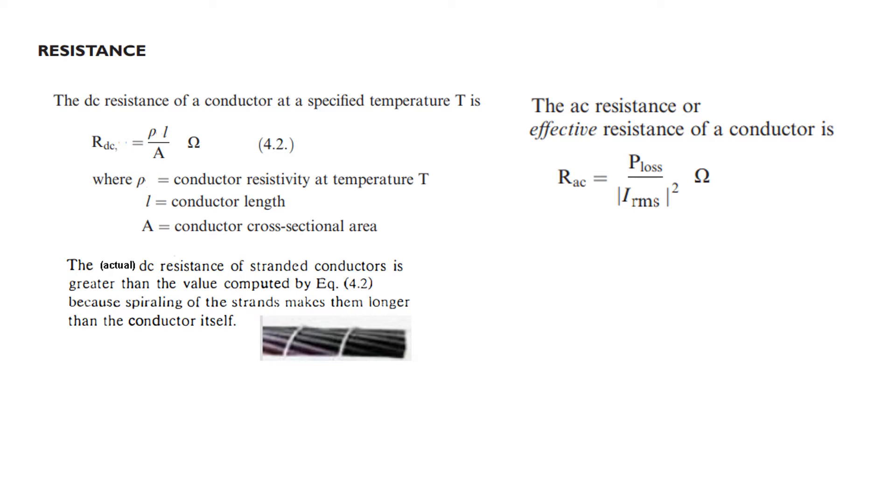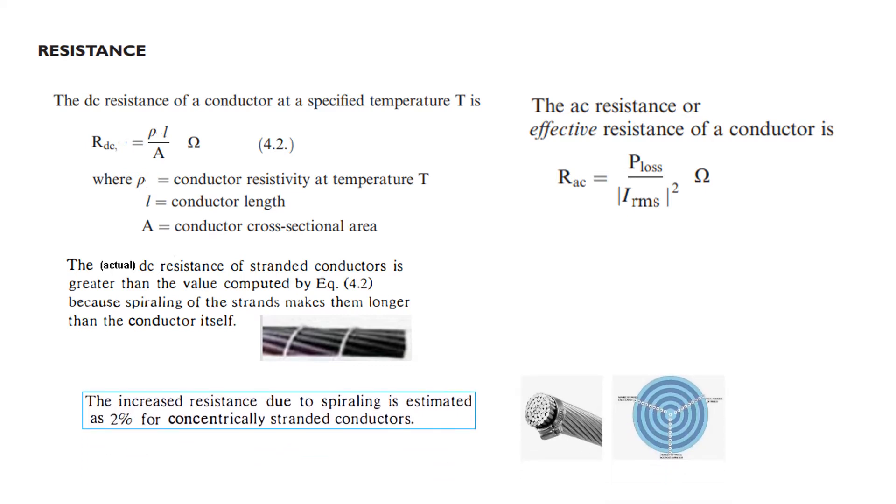There is a simple technique to cater for that, and that is we add 2 percent. The increased resistance due to spiraling is estimated as 2 percent for a concentrically stranded conductor, conductors which are stranded around the center, like this and as shown here.